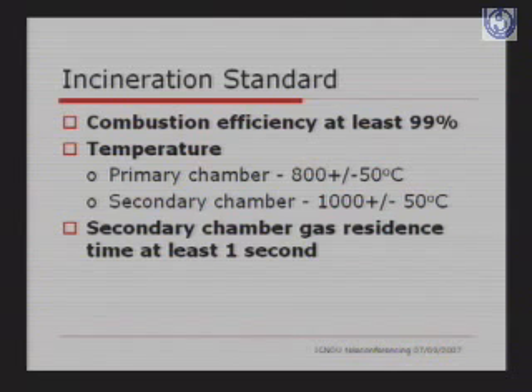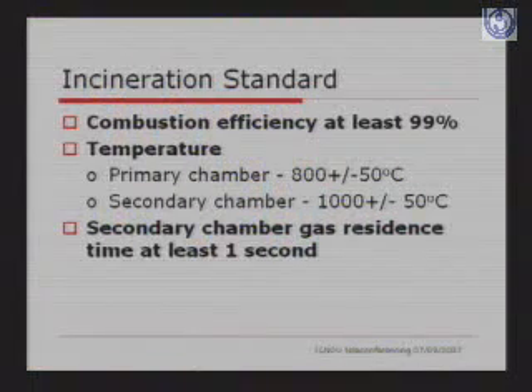And then the secondary chamber, it's basically where the gases that are coming out of the burning of the waste are held. They have to be there with oxygen, because in the primary chamber the burning is without oxygen, and in the secondary chamber the burning is with oxygen. Here the gases have to be there for at least 1 second. The gas residence time in the secondary chamber is at least 1 second, and here we have certain pollution control equipment, the scrubbers and all that have been installed, where we try not to emit the dangerous gases into the air. And there's a 30-meter chimney that has to be there with the incinerators, so that it's disposed of into the high air.